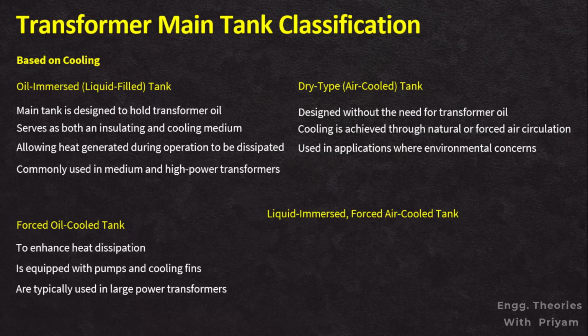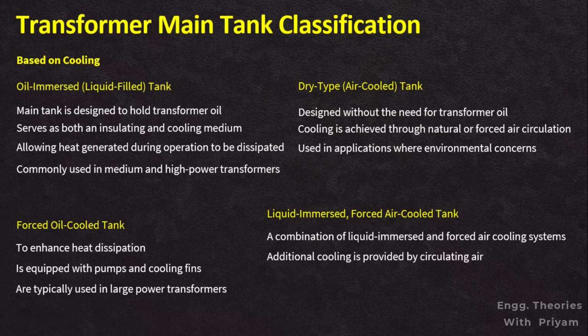Liquid immersed forced air cooled tank. In certain transformer designs, a combination of liquid immersed and forced air cooling system may be employed. The main tank contains the transformer oil for insulation, while additional cooling is provided by circulating air through cooling ducts or fins installed within the tank. The hybrid cooling offers the benefits of both oil immersed and air cooled transformers, providing efficient heat dissipation and insulation.